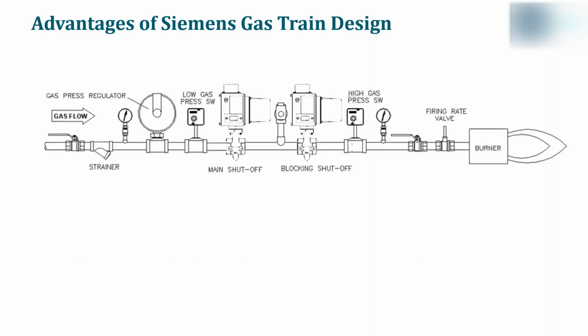So first, let's take a look at the traditional gas train that everyone is familiar with. In this gas train, you'll first notice that there is a total of 11 connections between the regulator and the high gas pressure switch. Each connection presents a potential leak point. Now, let's assume that we have a 500 horsepower boiler with 5-pound gas supply pressure. The majority of the pressure drop occurs at the regulator. If the burner requires 20 inches manifold pressure, the regulator will drop the pressure, say we'll drop it from 5 psi to 23 inches. This is set slightly higher to compensate for the pressure drop across the safety shutoff valves. Now, manufacturers will normally increase the size of the traditional safety shutoff valves to compensate for additional pressure drop through the SSOVs.